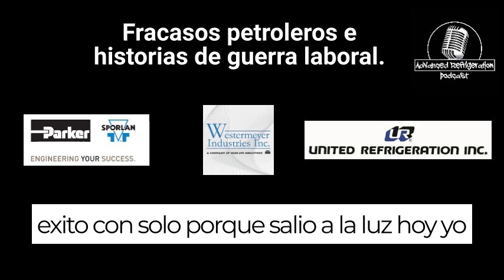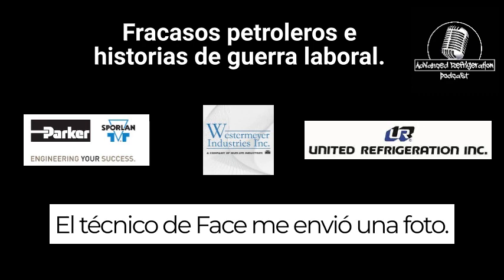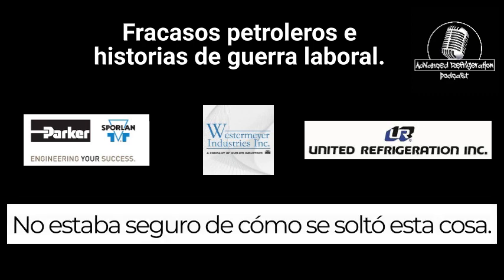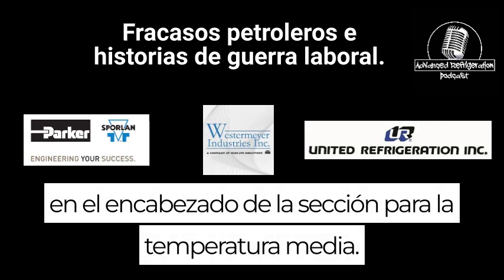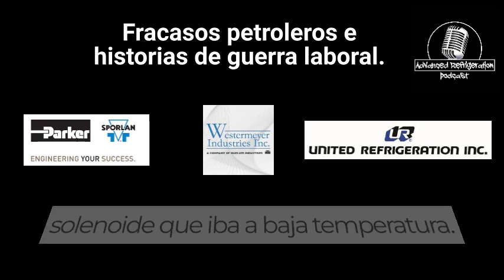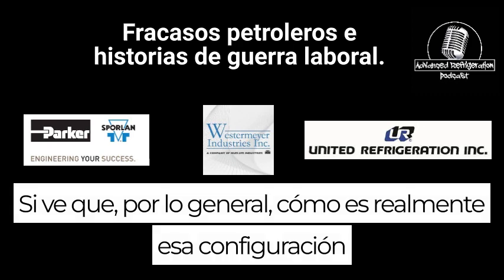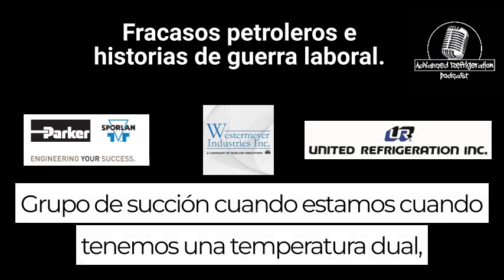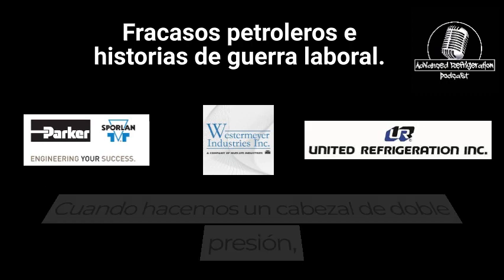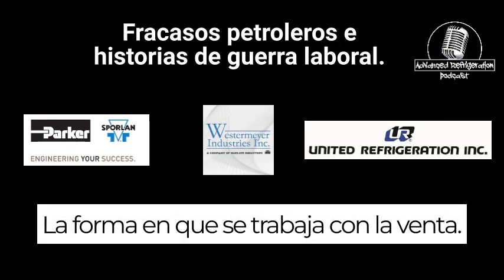Because it came to light today, I will be putting up a picture on the Advanced Refrigeration Podcast page. A technician sent me a picture. He wasn't sure how this thing was split down. They had a line coming from the OCV going into the suction header for the medium temp, but also in parallel with it, they had a solenoid that was going to the low temp. If you do see that, remember, we always want to be at the highest suction group when we have a dual temp header. When we have a dual pressure header, we want to be at the highest pressure.